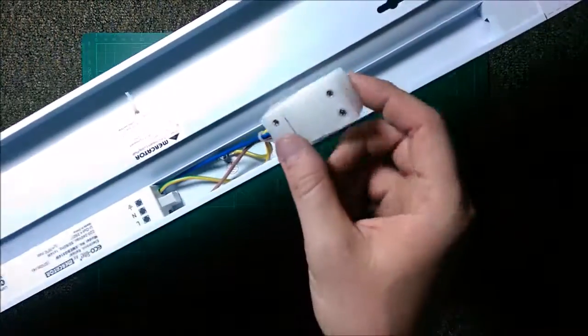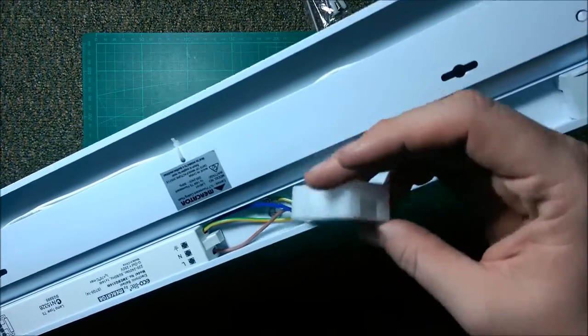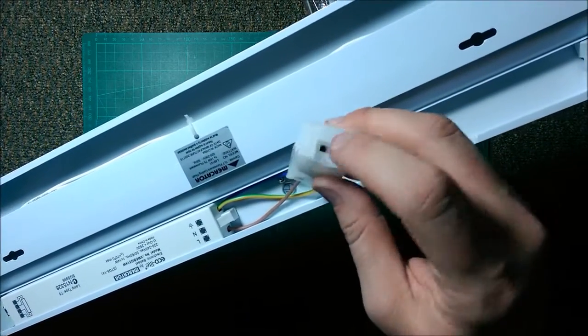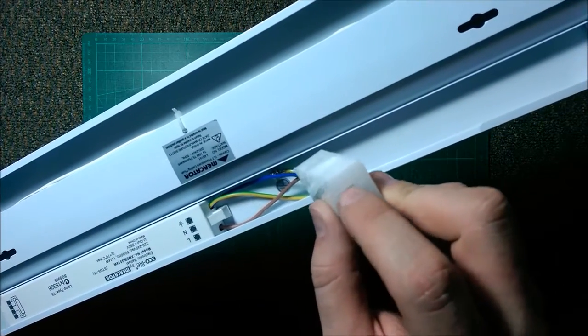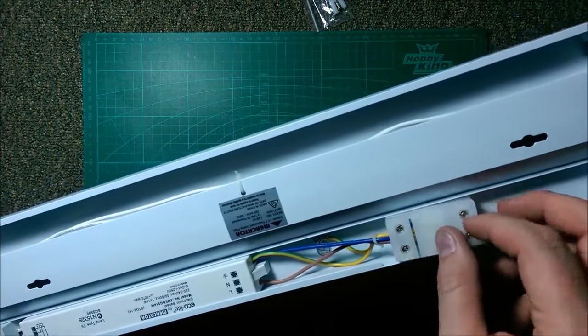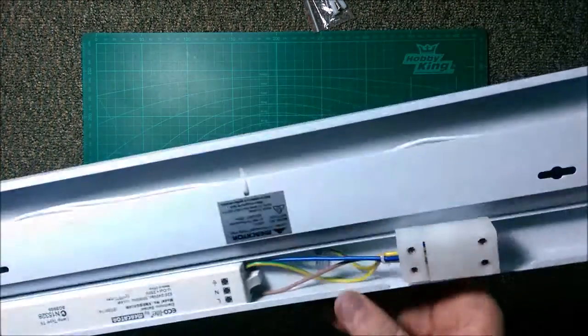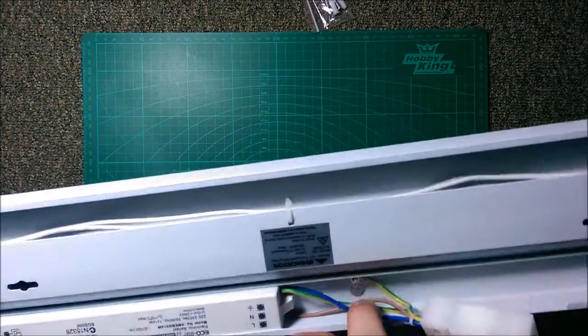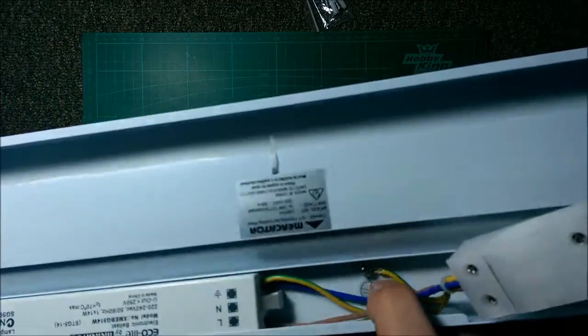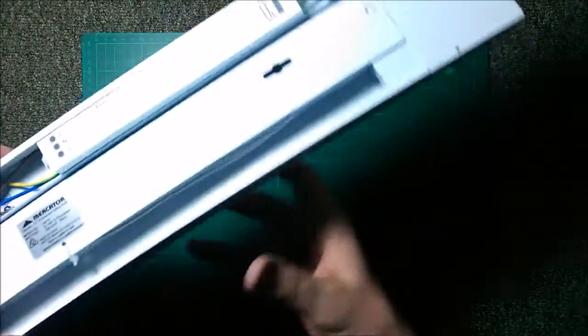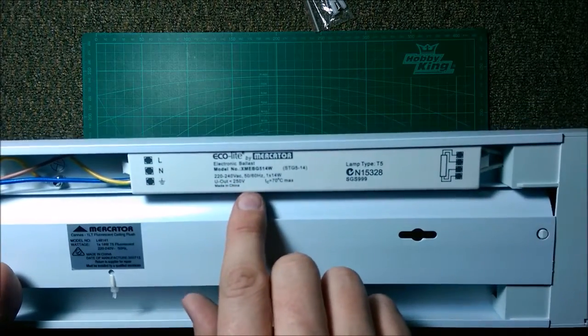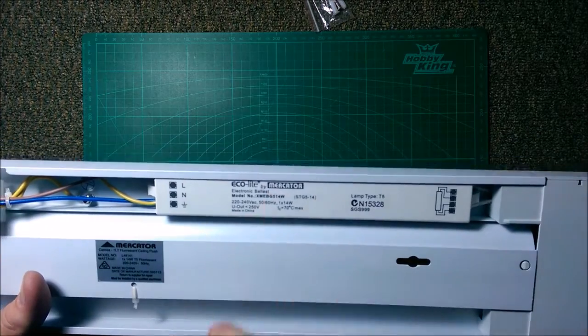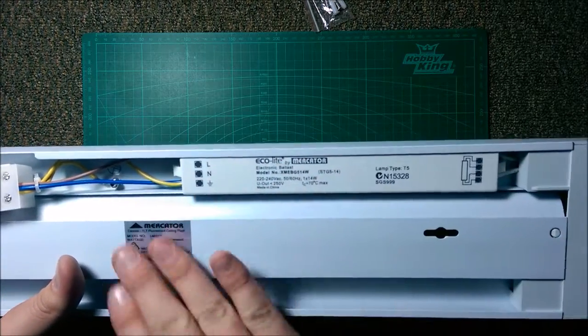A couple of mounting screws and the sockets and looks like a shrouded terminal block there. If you have a look it's also got some cable retention there which is good. It's a metal powder coated enclosure or chassis so it's got its earth pin there which is crimped and screwed down so it's all good. This is the ballast, 220 to 240, 50 or 60 hertz, 70 degrees max. These things generally get just warm to the touch.